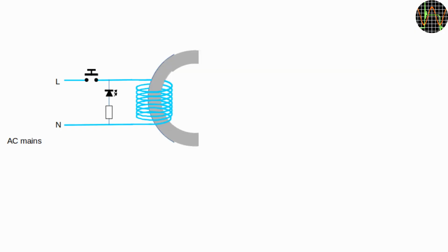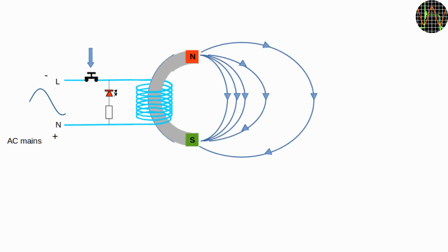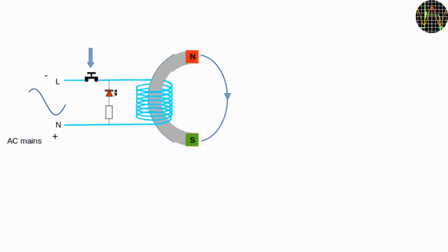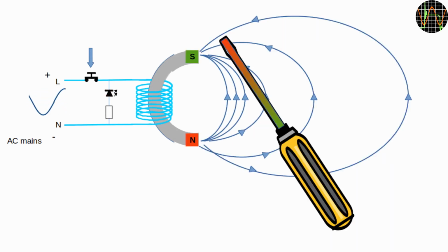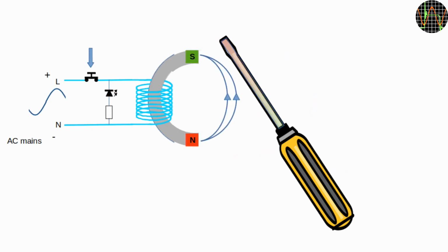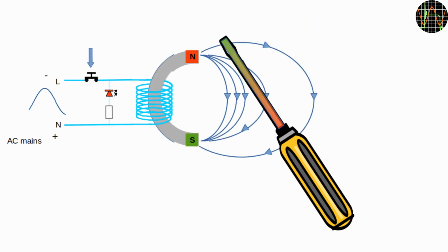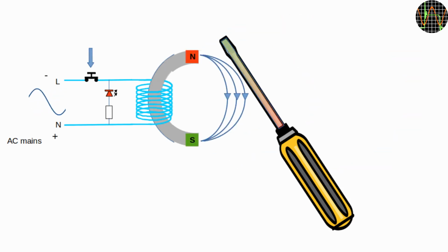What the demagnetizer does when you press the button is to generate a powerful magnetic field that changes its north-south direction 50 or 60 times per second and a sinusoidal intensity variation. Any ferromagnetic object that you bring into this field is magnetized and follows along, doing the same changes in polarity and intensity. But that does not demagnetize the object by itself, far from it. As soon as you let go of the button, the field disappears and whatever object you try to demagnetize keeps the last magnetic orientation and field strength it has experienced.